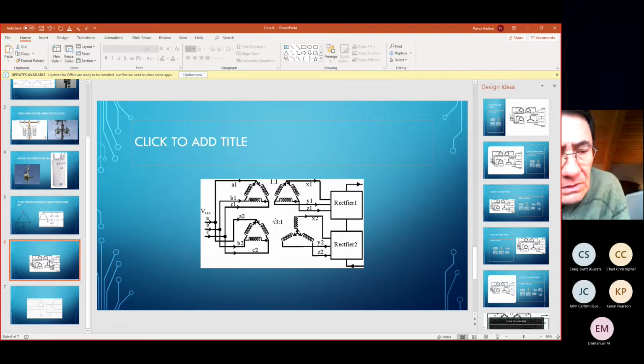Voltage distortion power factor, not a problem. Current waveform distortion power factor, the third item in total harmonic distortion and total power factor, current waveform distortion power factor is the concern. And the way that we are going to fix that, first thing we pull out of the holster is inductive reactance, copper wound around iron, because a capacitor is a voltage shock absorber, an inductor is a current shock absorber. And therefore, when you have aberrant current waveform, you pull out a shock absorber. And the first thing that you do is you throw an input line reactor onto the front end of the drive. Now let's put some numbers on this.